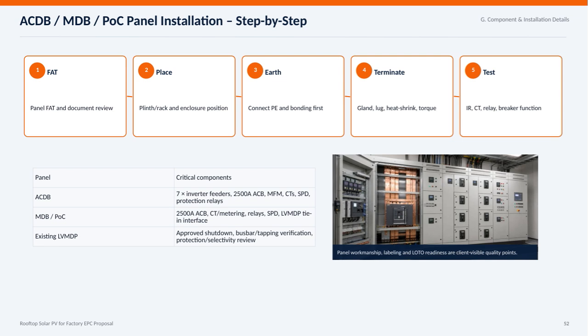The critical components vary by panel type. The ACDB includes 7 inverter feeders, a 2500A ACB, MFM, CTs, SPDs, and protection relays. The MDB and POC panels feature a 2500A ACB, CTs for metering, relays, SPDs, and the LVMDP tie-in interface, while the existing LVMDP requires an approved shutdown, busbar and tapping verification, and a protection and selectivity review. Throughout the process, panel workmanship, labeling, and lockout/tagout readiness are essential quality points visible to the client, underscoring our commitment to safety and reliability.